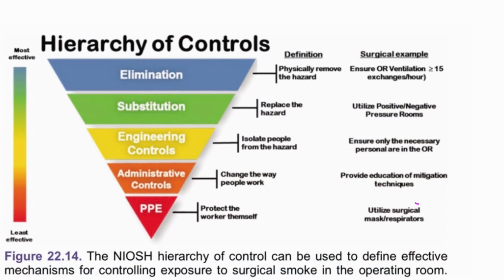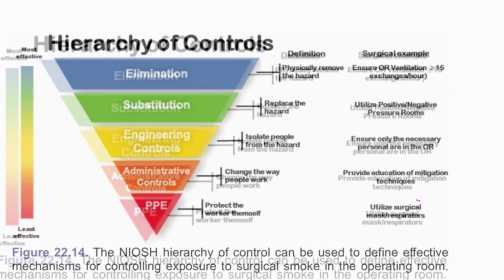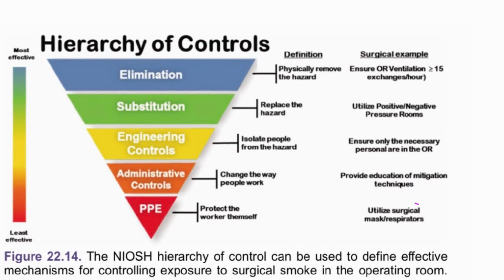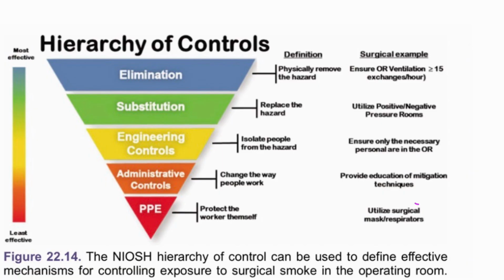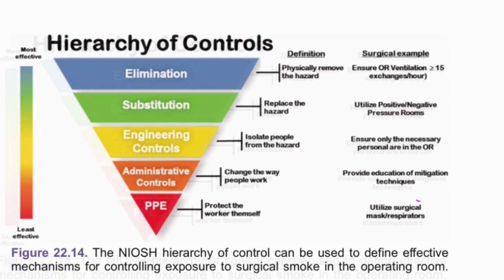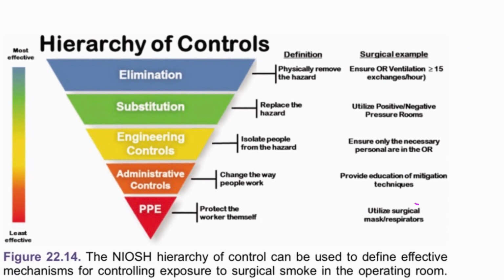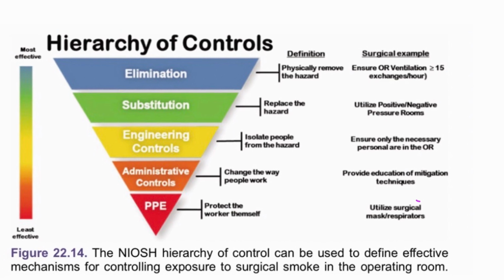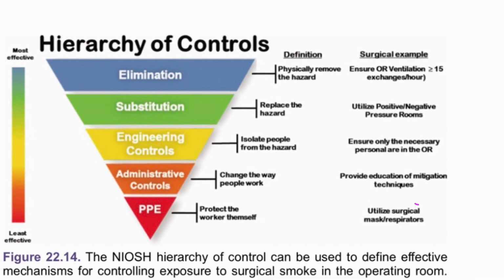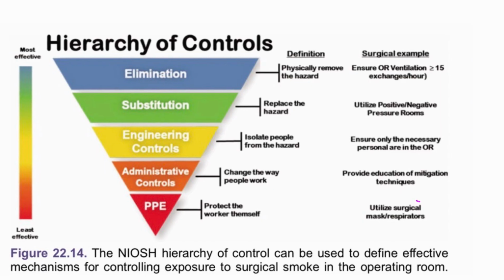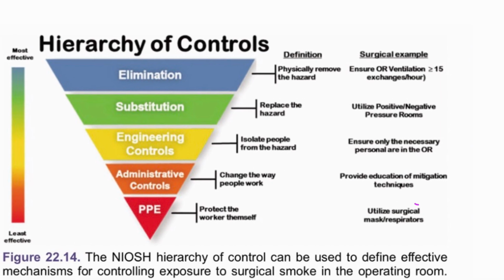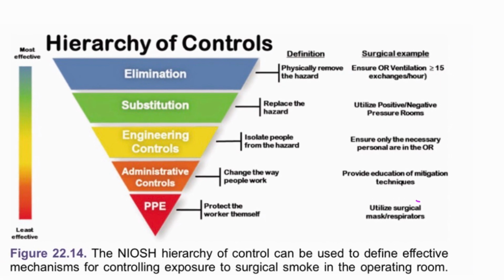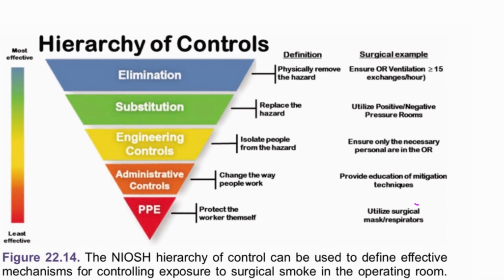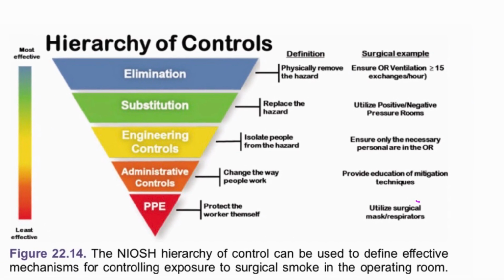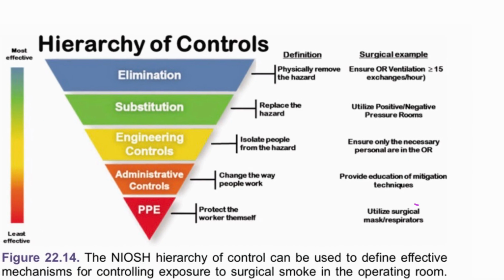So the controls need to be taken care of. PPE, personal protective equipment, protects the workers themselves, and the administrative controls change the way people work, educate them, and mitigate techniques. The engineering controls isolate people from the hazard; ensure only the necessary people are in the OR. Substitution replaces the hazard; utilize positive and negative pressure rooms. Elimination physically removes the hazard; ensure OR ventilation of more than 15 exchanges per hour.